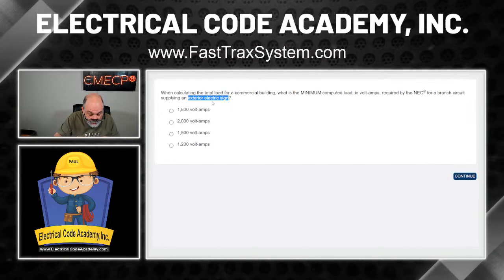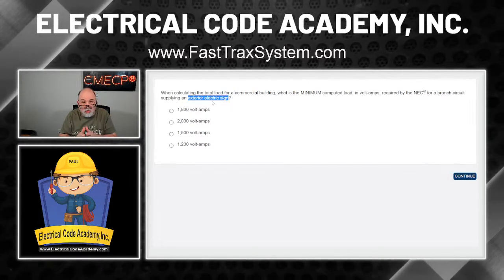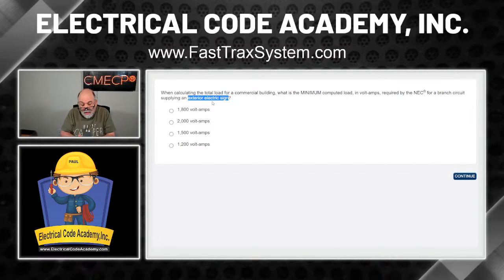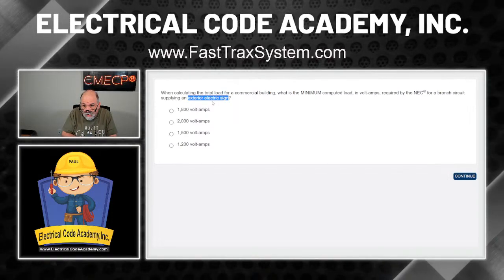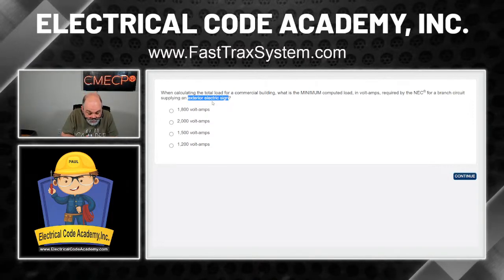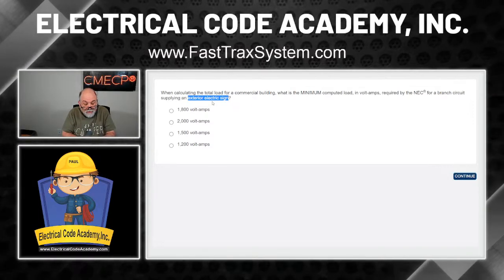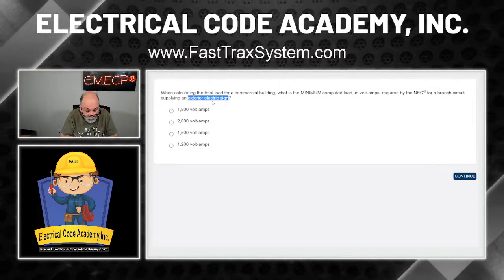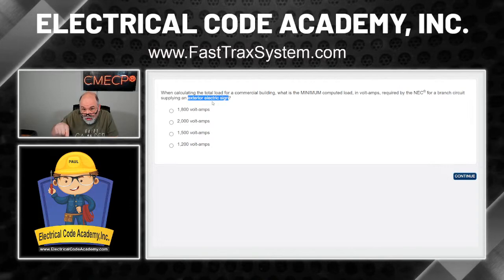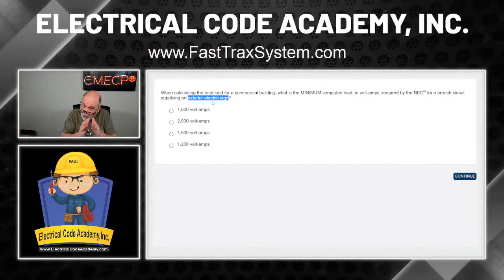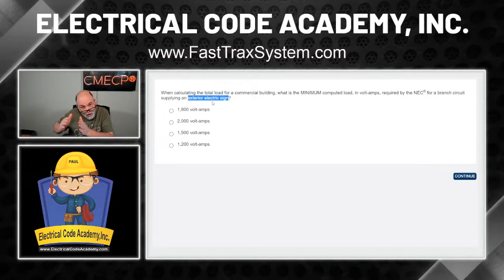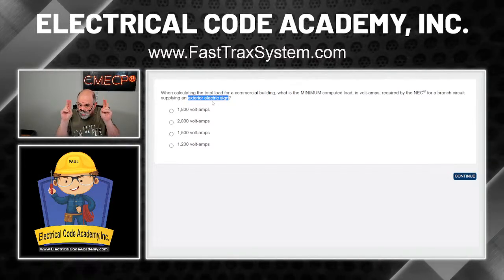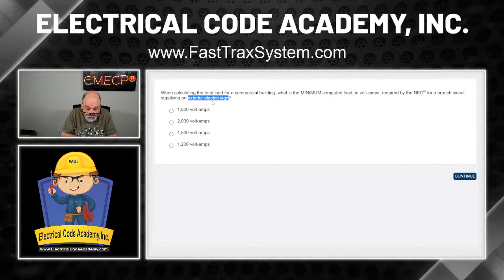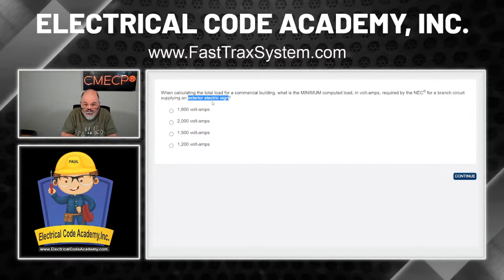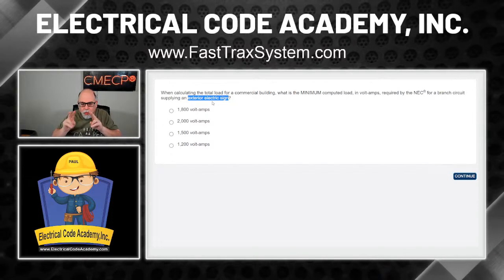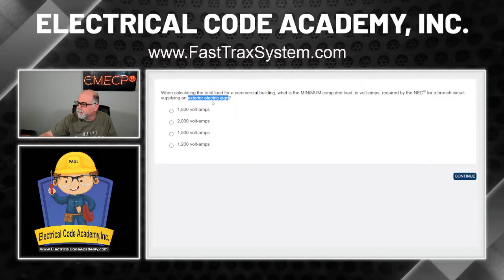Now, the first thing I'll also remind you is that electric signs is under Article 600. So if we don't find the answer that we want in 220.14, in this case it looks like 220.14(F), it also has a reference to 600.5 as well when it comes to branch circuits. So you jot that down. We're going to be working in either 220 or 600, but we're going to go to the most obvious. Since we're doing a calc, we're going to go to 220.14(F) first. So you've got your work laid out for you there. Let's go on and go over to the code.